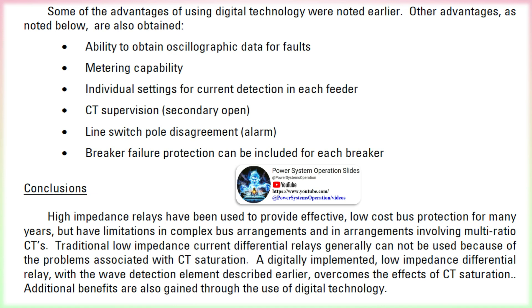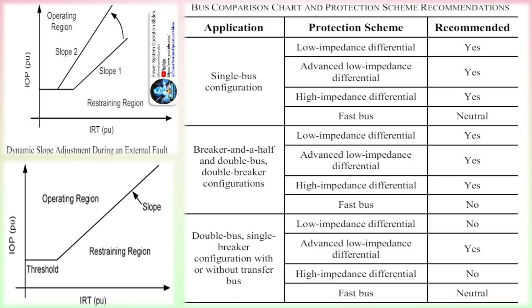A novel bus configuration program is used with this relay to allow the user to input their specific bus arrangement. The program then generates wiring diagrams along with specific instructions to allow the relay to be built. The relay contains all necessary auxiliary CTs to allow ratio matching in the event that different ratio CTs are involved. Additional advantages of digital technology include: ability to obtain oscillographic data for faults, metering capability, individual settings for current detection in each feeder, CT supervision for secondary open, line switch pole disagreement alarm, and breaker failure protection for each breaker.